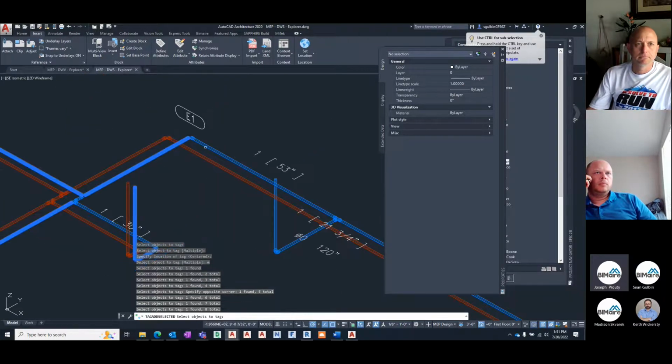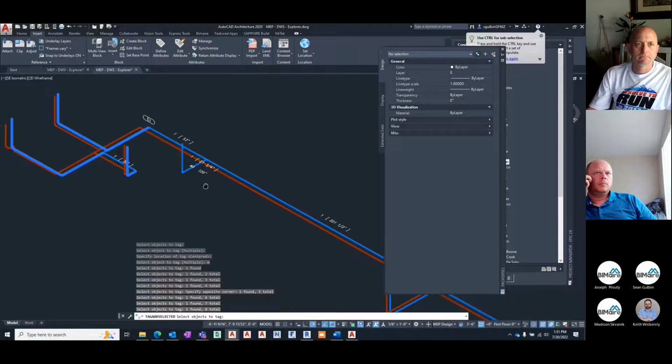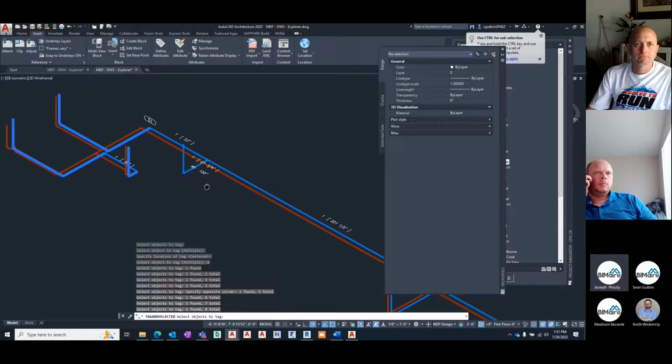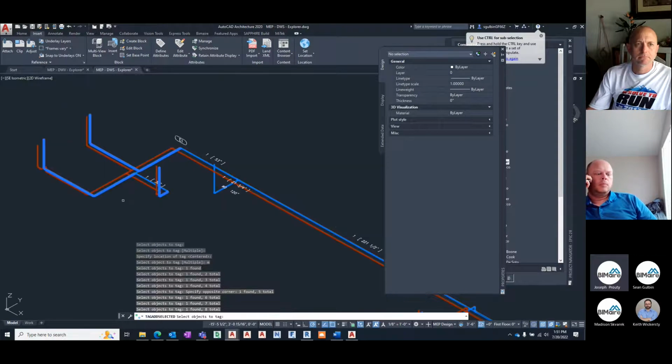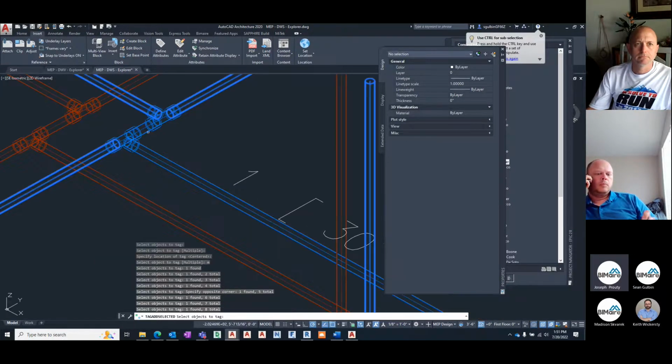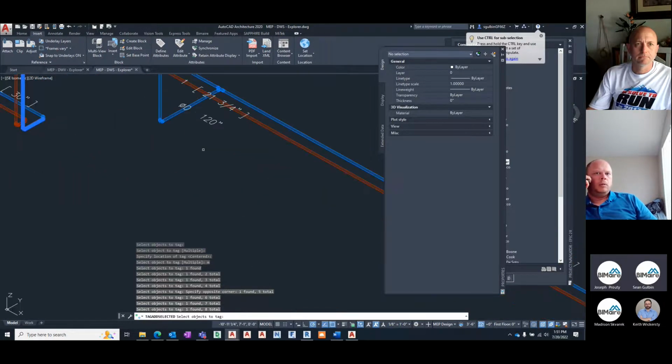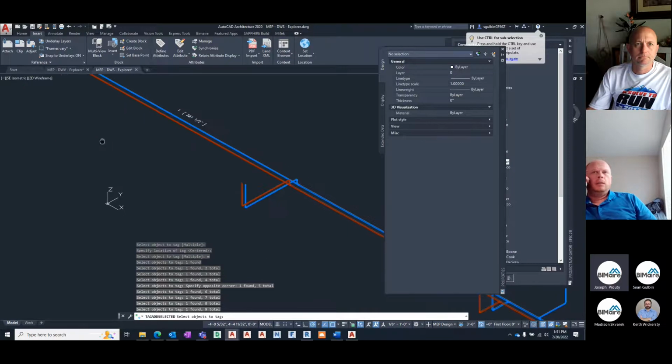And that's another thing you do: we don't tag every single pipe. You only tag pipes that are longer than the tag. They don't bother with anything less than 12 inches, give or take, right around that area. In other words, if the tag couldn't fit next to the pipe, we don't usually tag the length of it. That's how it goes.